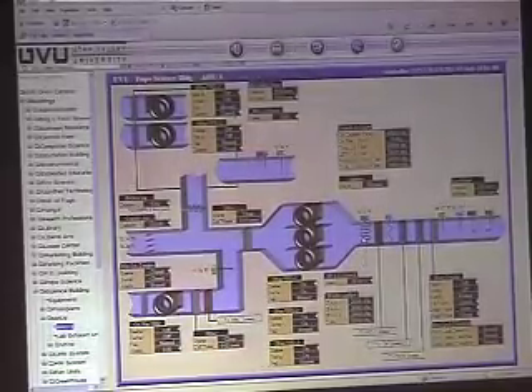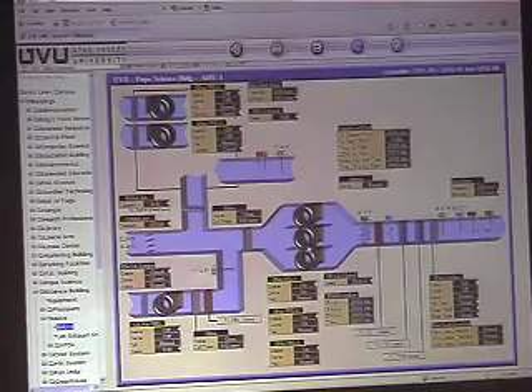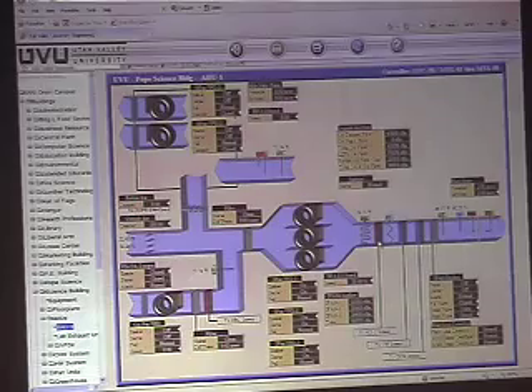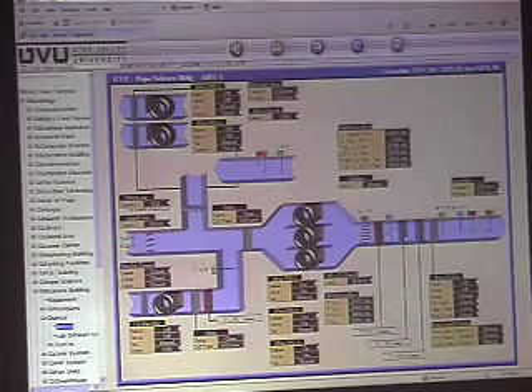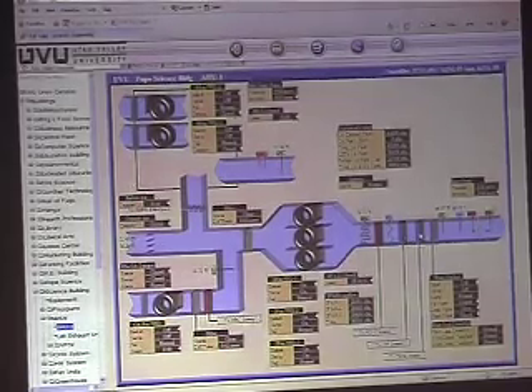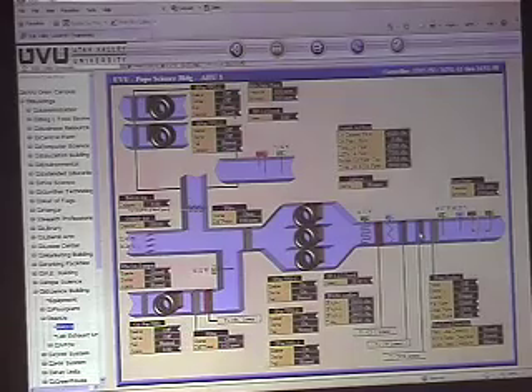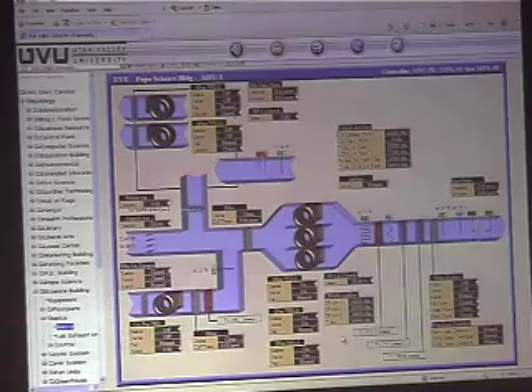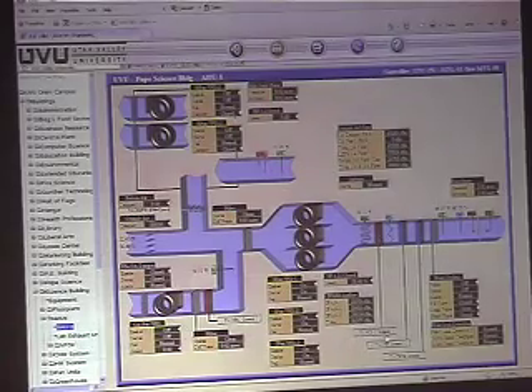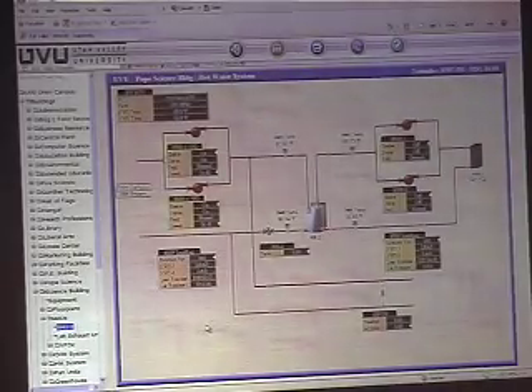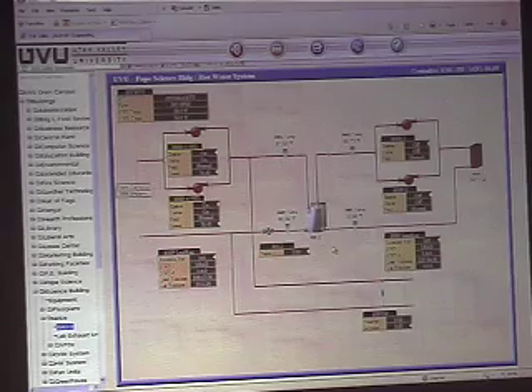There's a mixed air sensor here right after the supply fans, and your hot water coil here, condenser water coil, and your chilled water coil. This hot water coil is fed from the heat exchanger. If we go to this screen here, you can see the heat exchanger equipment here for this building.